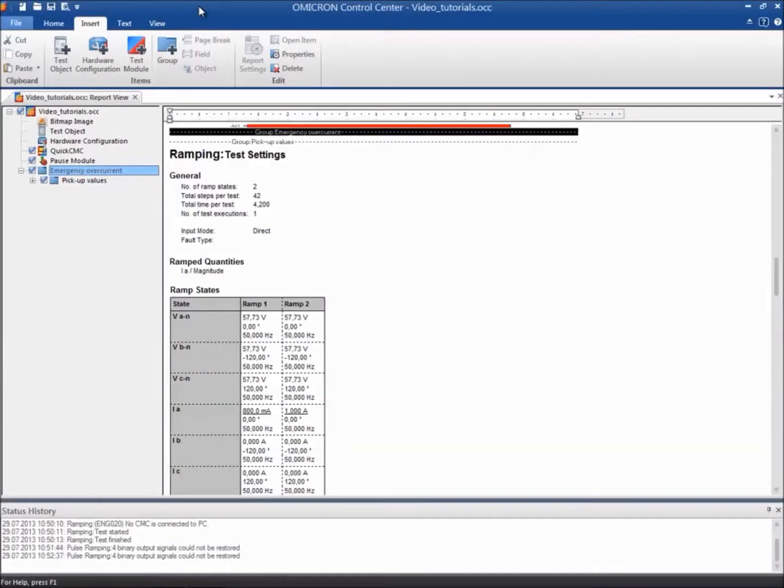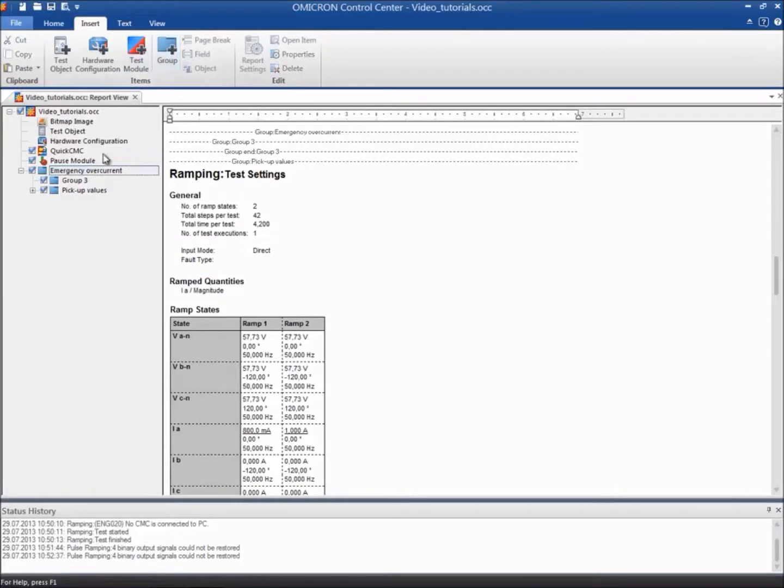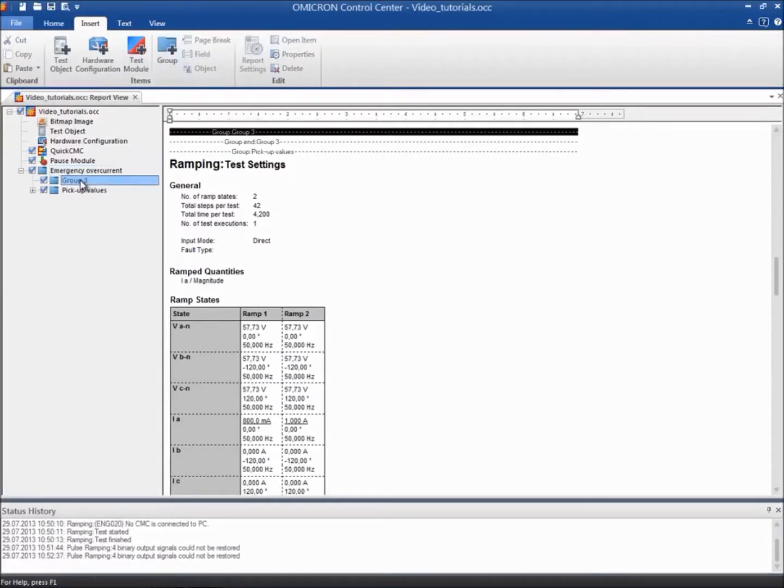As we are using this module to test the trip time of the Overcurrent Protection function, we can proceed to create a new folder called Trip Times in our OCC file.